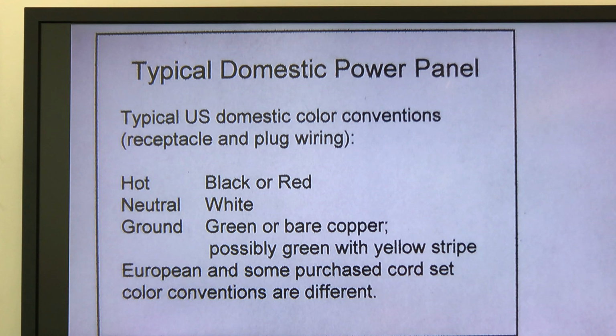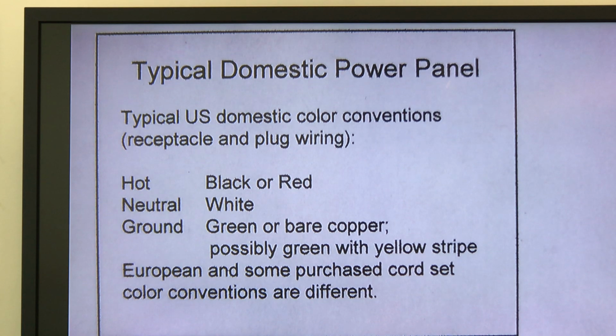The typical color conventions for an electrical installation in a dwelling or an apartment, whether it's a receptacle or a plug cable: the hot wire is typically black or red. Neutral line is typically white. And then the ground may be a green wire, or it may be bare copper. Sometimes, mostly in a cord set, in other words, the plug that has a pigtail off of it, those can be green with a yellow stripe. But in general, black or red is going to be the hot wire. White is going to be the neutral. And then you'll have either a green insulated wire, a bare copper wire, or maybe green with a yellow stripe. And that'll be your ground.